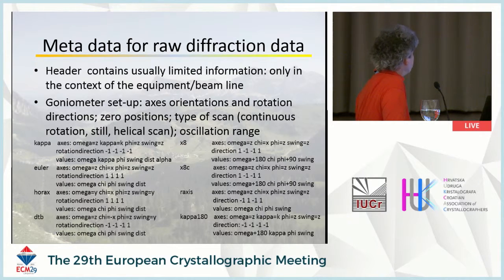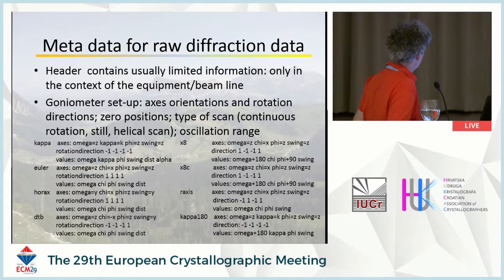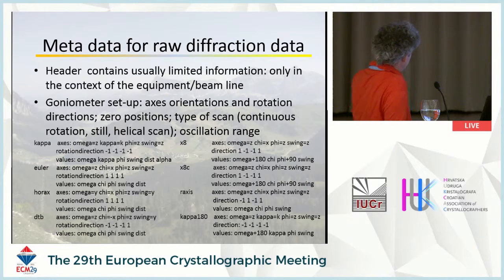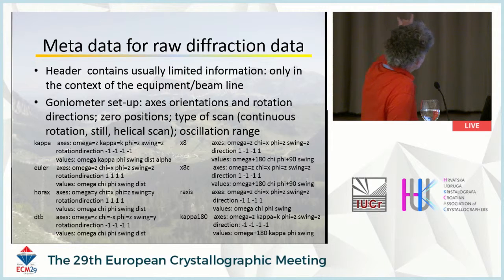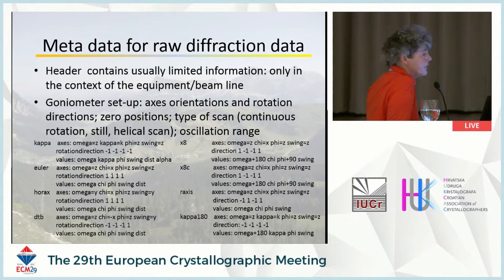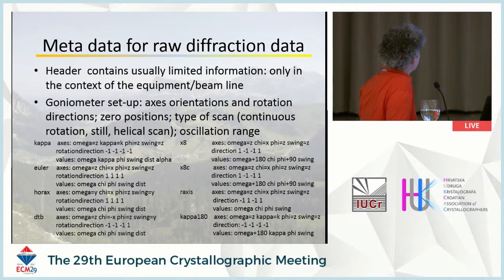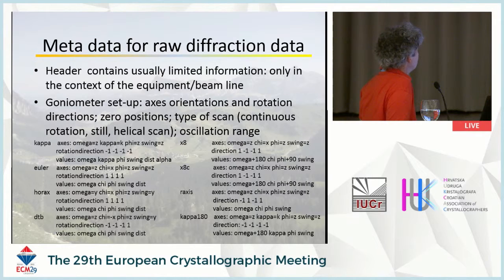EVAL recognizes eight types of goniometers, and you can see that the definitions of axes — for instance omega — can change from goniometer to goniometer: sometimes it's the Z axis, sometimes the Y axis. Rotation directions can also change; for example, comparing the old Nonius kappa goniometer to the new Bruker X8, the rotation direction of omega is reversed. This is all prior knowledge needed to properly interpret goniometer angles.